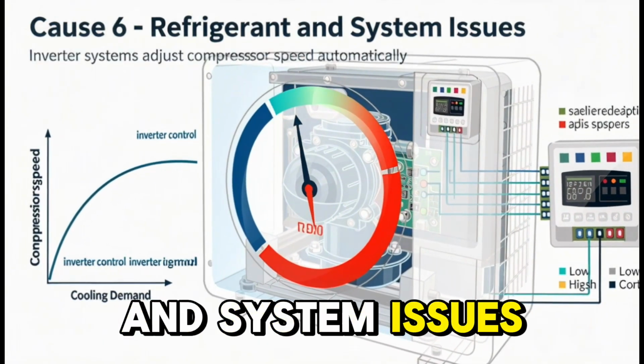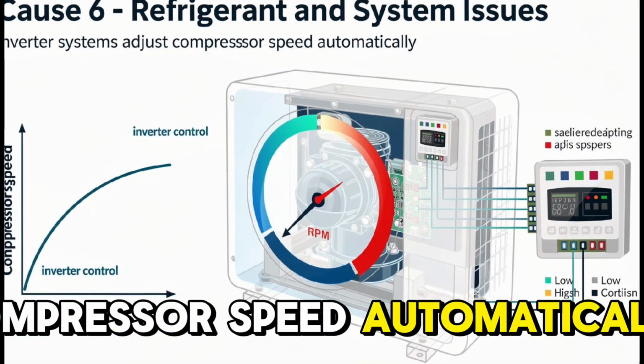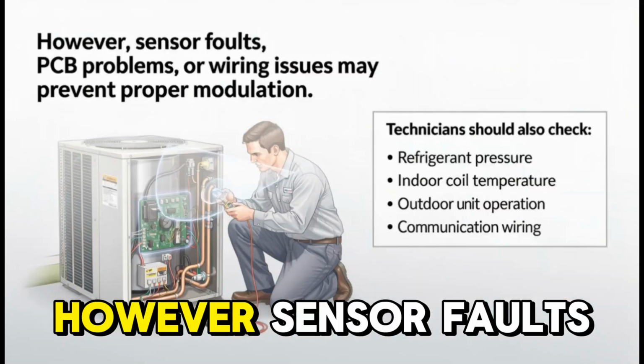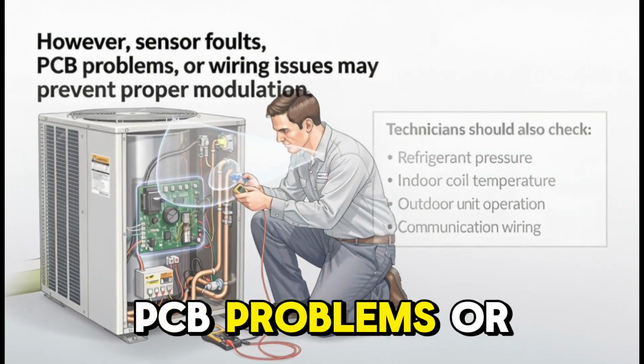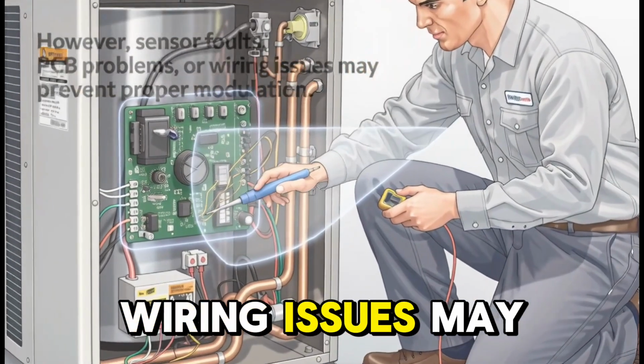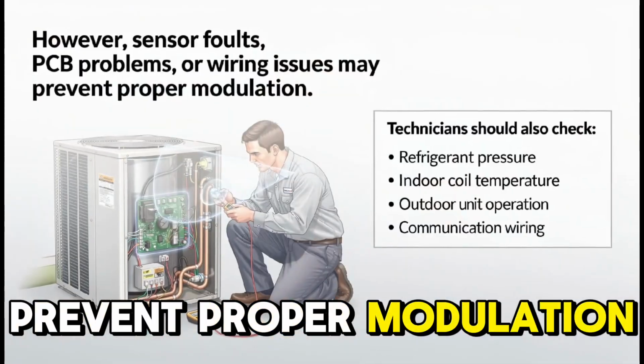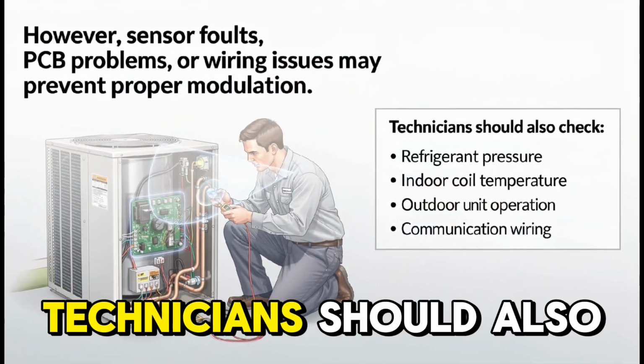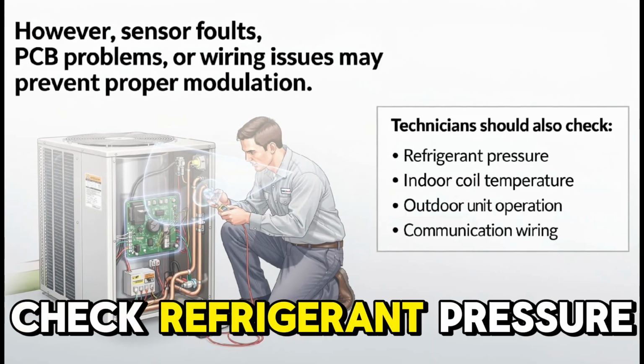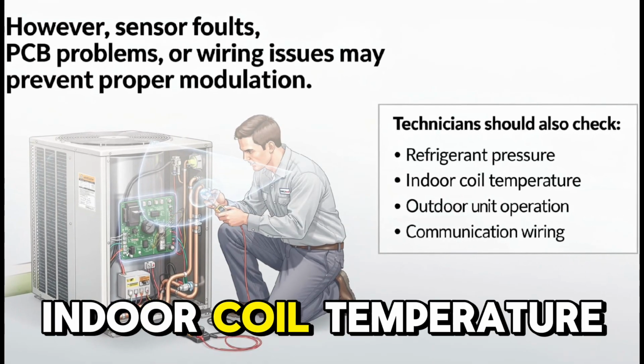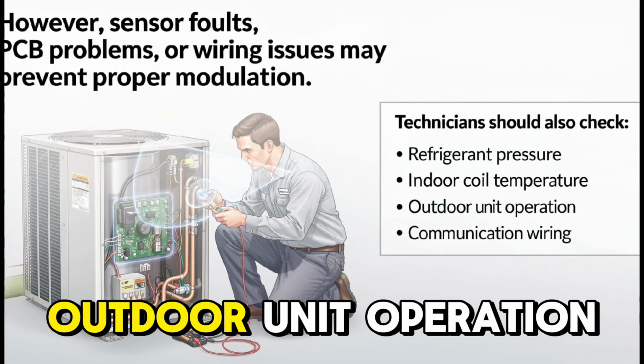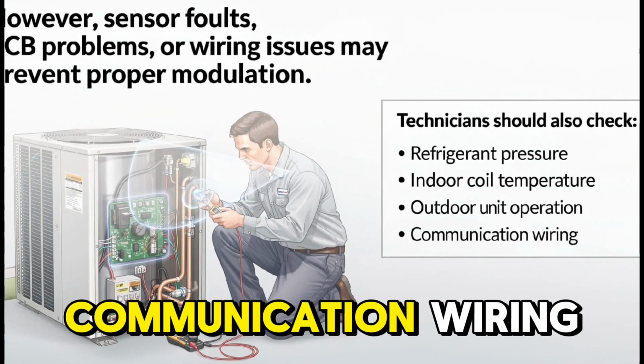Cause 6. Refrigerant and system issues. Inverter systems adjust compressor speed automatically. However, sensor faults, PCB problems, or wiring issues may prevent proper modulation. Technicians should also check refrigerant pressure, indoor coil temperature, outdoor unit operation, communication wiring.